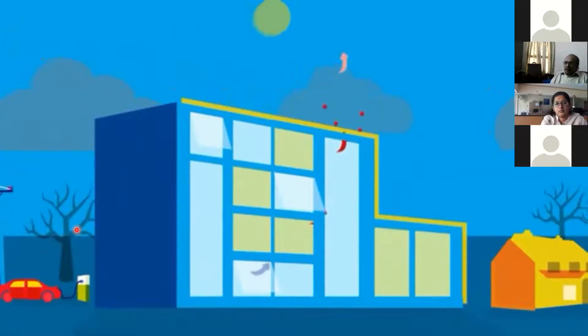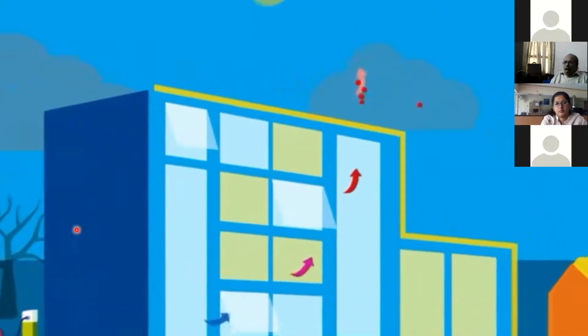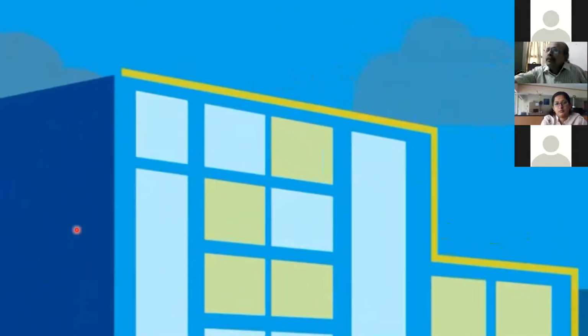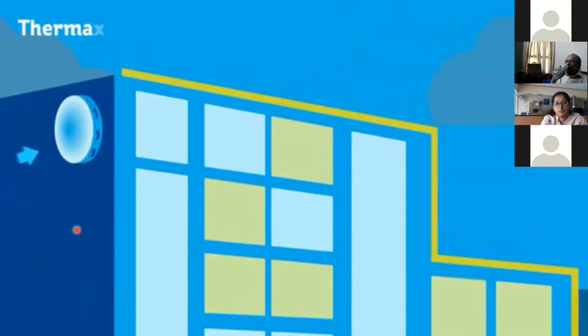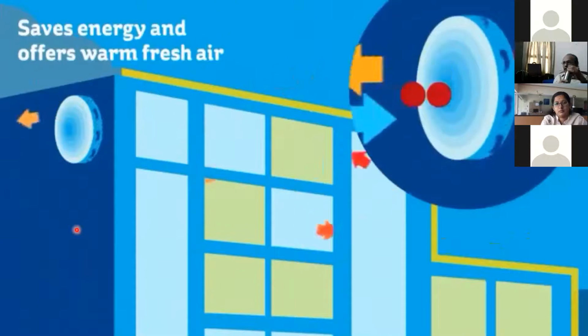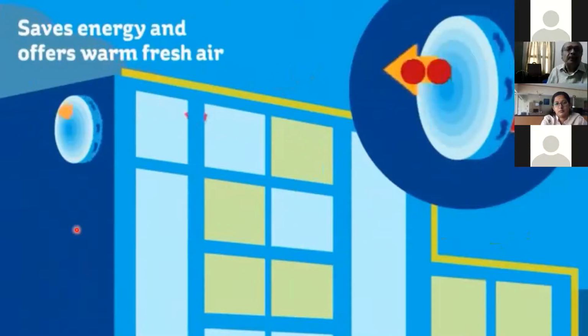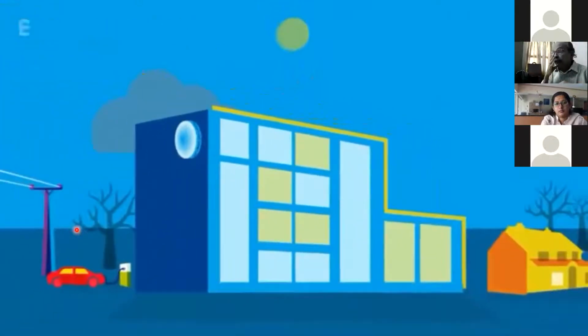The heat recovery system works by closing the office windows during cold weather and delivering air through a special wheel called a thermal wheel. This wheel contains lots of very small metal airways that absorb energy or heat from the outgoing air. As the wheel spins, it transfers heat from the expelled air to warm up the cold incoming air. This saves energy and offers warm, fresh air.